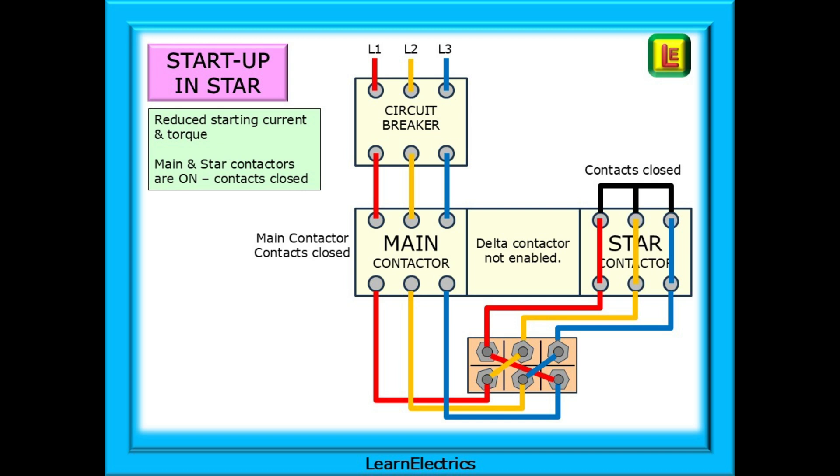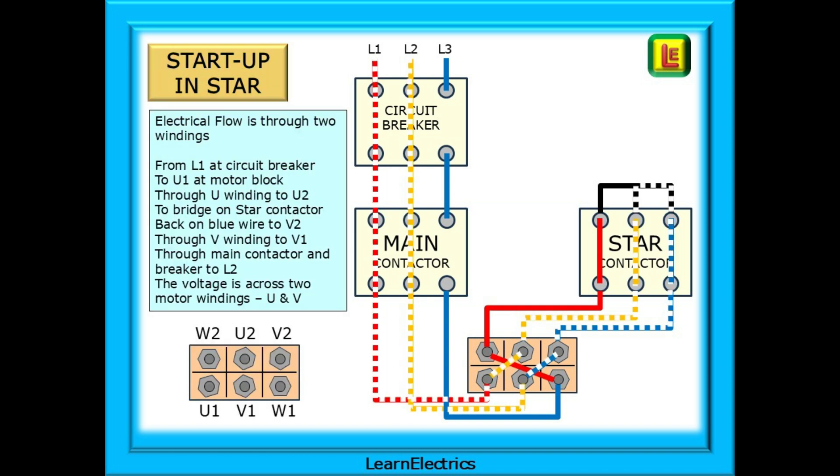Let's start up the motor in star configuration. This will give a reduced starting current and torque. The main and star contactors are on. The contacts are closed. The delta contactor has not been enabled and takes no part in the startup. Electrical flow is through two windings in series at startup. From L1 at the circuit breaker to terminal U1 at the motor block, then through the U winding inside the motor to terminal U2, then to the bridge on the star contactor and back along the blue wire to terminal V2. Now through the V winding to terminal V1, and then through the main contactor and breaker to L2. In star configuration, the supply voltage is across two windings, U and V in this example.